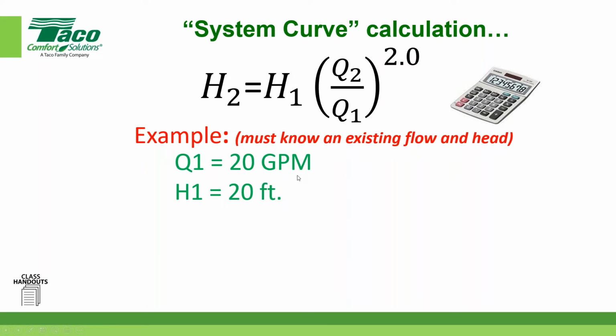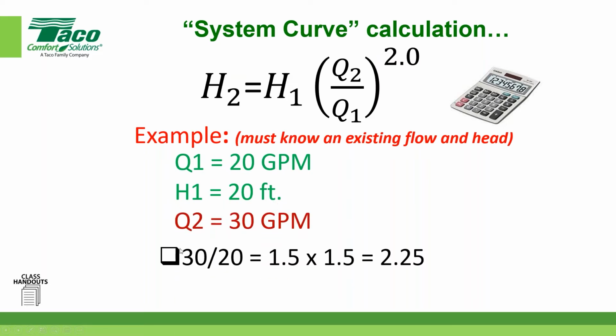I have to establish what the first flow was and what the head was at that flow. Now here's the new flow, 30 gallons a minute. You take 30, the new gallons a minute, divided by the old gallons a minute, which is all I'm doing up here. That gives me 1.5 that I square.